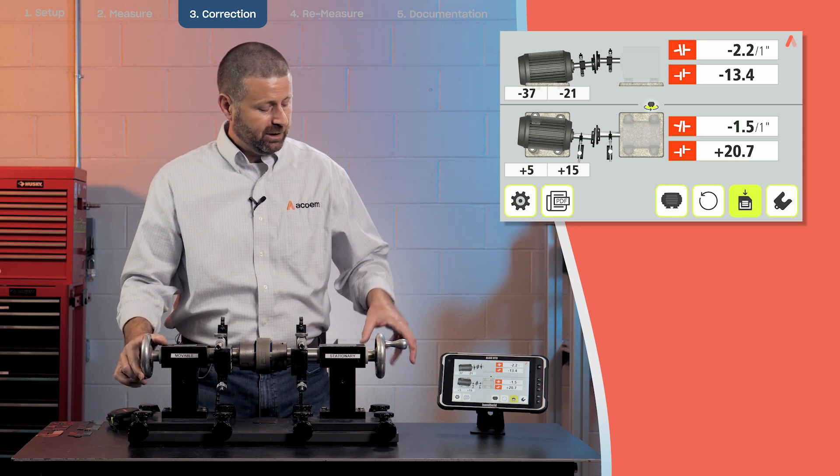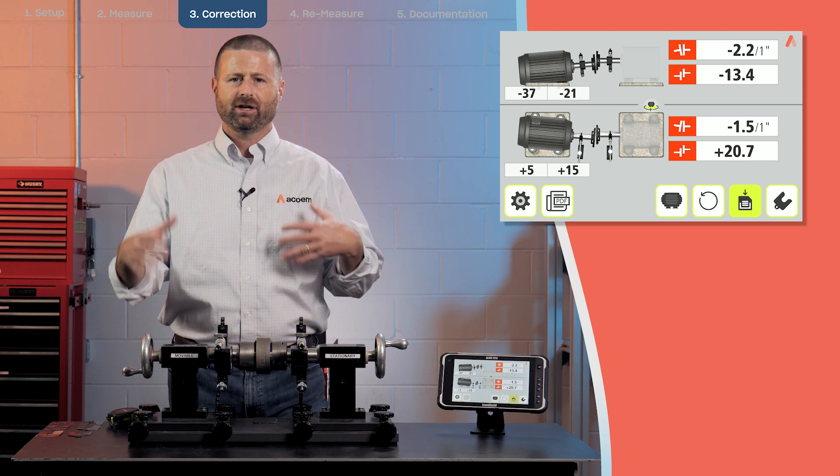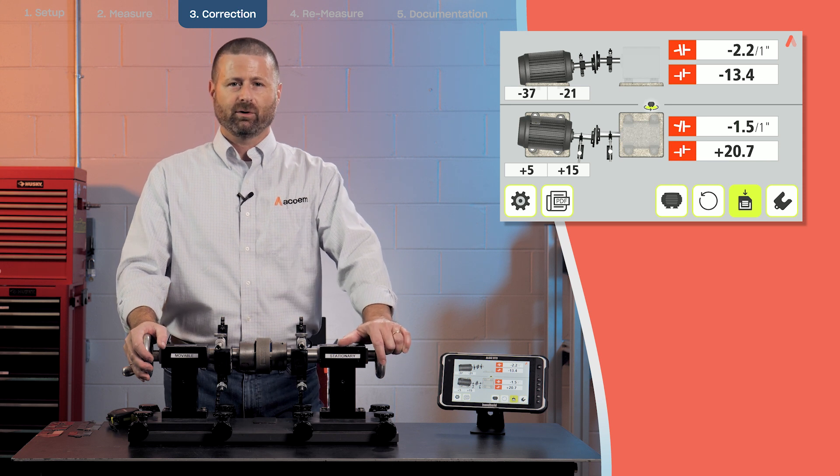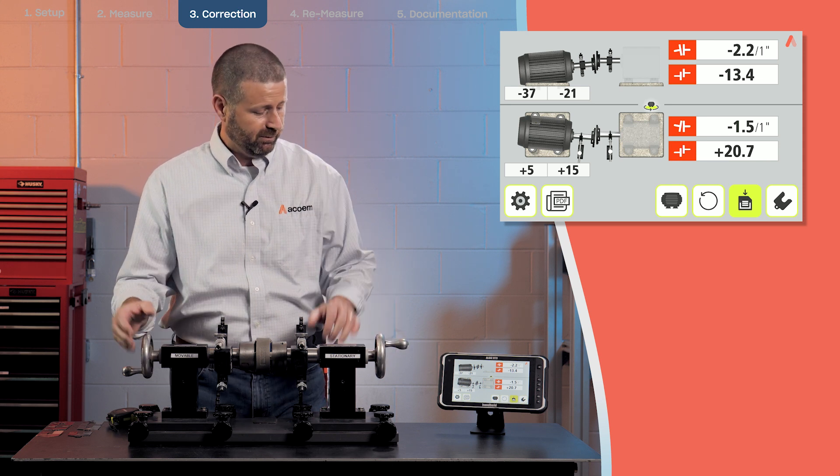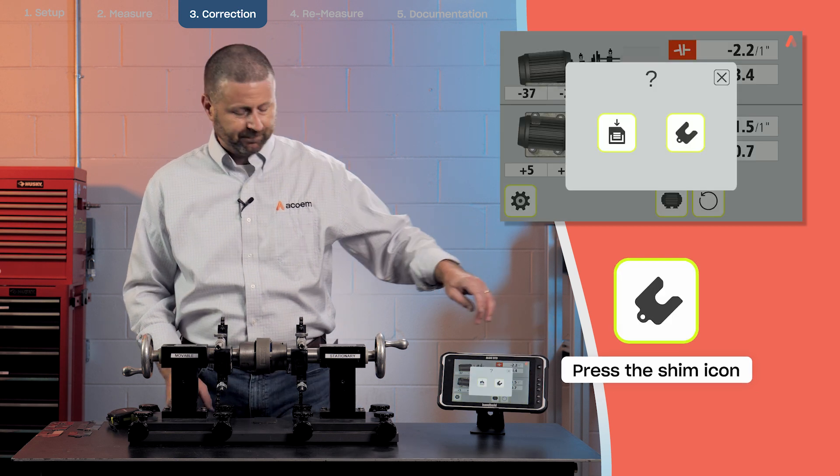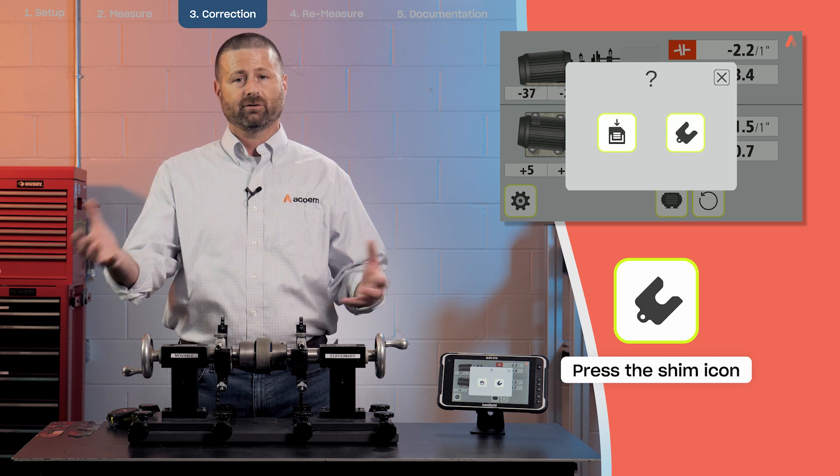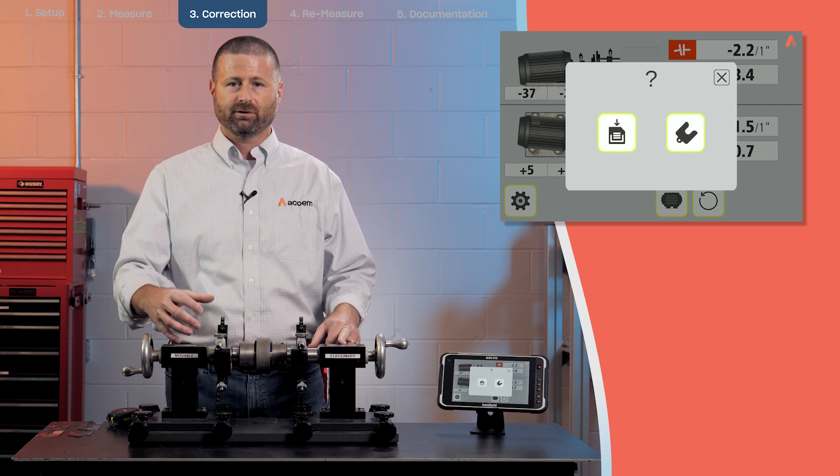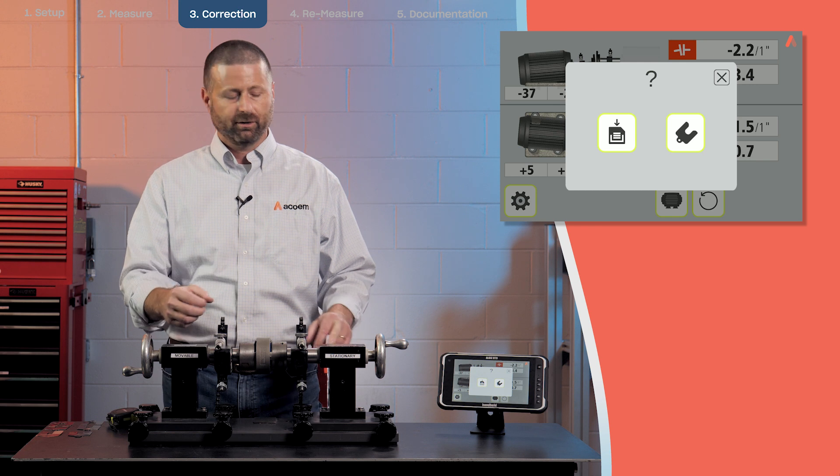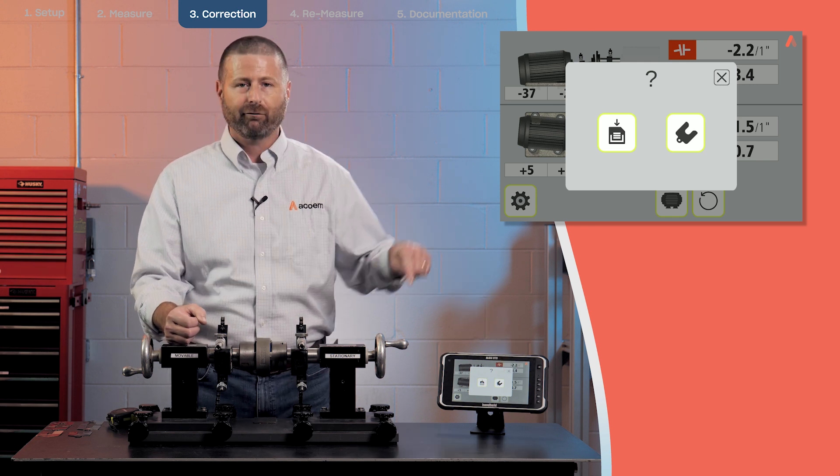At this point you see some positive numbers and some negative numbers. You'll see in the next step exactly what that's going to mean in terms of where we move the machine. So next I'm going to hit my shim icon because shimming is generally done first. My vertical adjustment is done first and horizontal adjustment is done second. That's why we call it vertizontal.